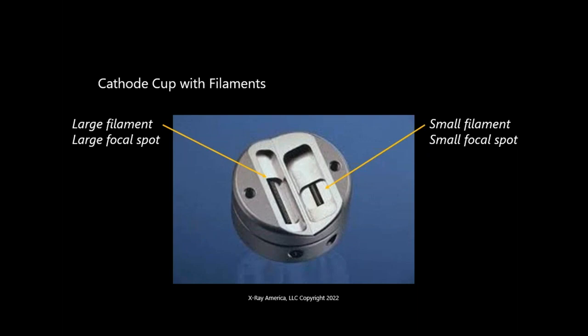Sure. The other thing that can happen is the tube might not be noisier in terms of dB level, but there's a quality to the sound. Some sound like a garbage disposal, and it can be objectionable even though it might not be loud. It's just a nastier, harsh sound. One thing to look at is the manufacturing side. It might be really loud this way, and then you turn it and there's no noise. If the manufacturer spec doesn't require them to test for noise, first of all, test for the noise.